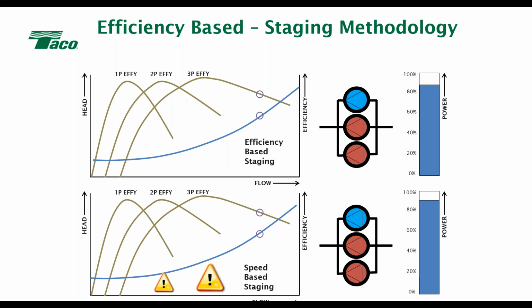Well, we understand that design capacity, the design load point, only happens about 5% of the time. So why would we want to design a system where the only time our energy is equal is when we're at that design point? We're going to spend most of our life at a part load condition. Doesn't it make more sense to design and operate your system for best efficiency at that part load condition, where it's going to spend most of its life?